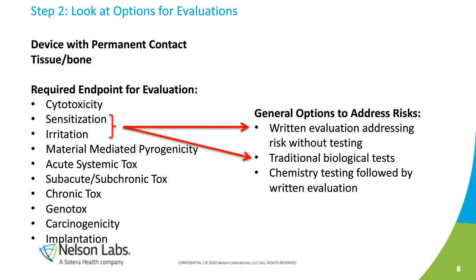So sensitization and irritation, this is one of these things that for a European notified body or an MDR remediation, first of all, we can do a written evaluation to address this without testing. Oftentimes, if the materials are very well known and all the contacting materials are known, then these can be screened and we can explain why there are no sensitizers or irritants there. If there is a gap that can't be addressed with pen and paper, then we would recommend the in vitro tests to spare animal life on that point. And we believe these tests are better than the in vivo tests. So for sensitization and irritation, there are options to address those.